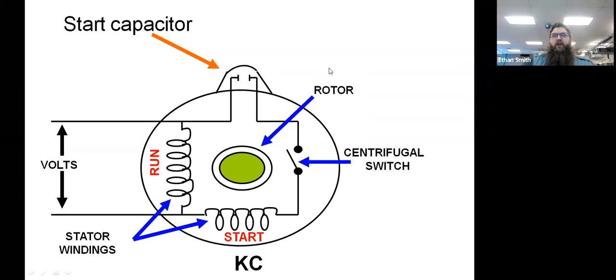Okay, from there we can get even more complicated. We can start adding capacitors to these things. So we've got a start capacitor in series with that start winding. While the start winding is physically out of phase with the run winding, the start capacitor will cause it to be physically and electrically out of phase with the run winding. So it gives it an even bigger kick. Of course, once that thing's up to speed, we want to drop it out. You'll see these a lot on air compressors, where once it's up to speed, it drops out. You see this on things like bench grinders, which will have that centrifugal switch and a start capacitor. So you've got a lot of start torque on it.